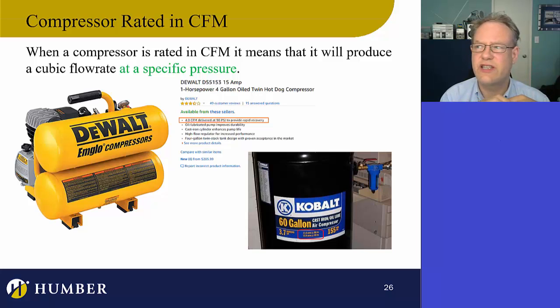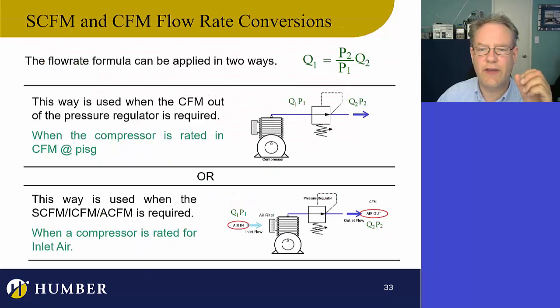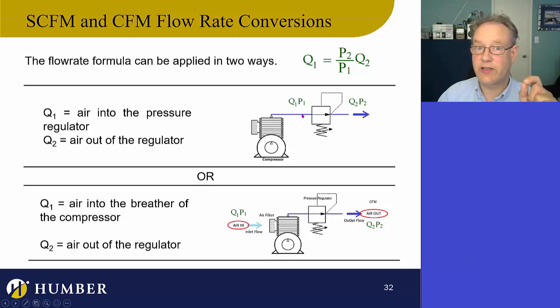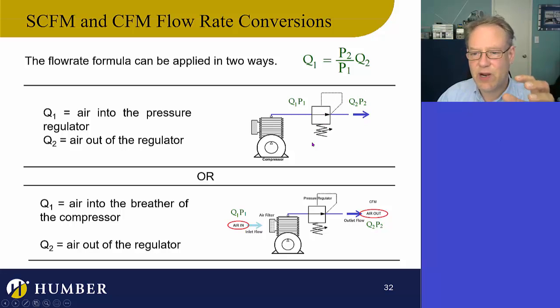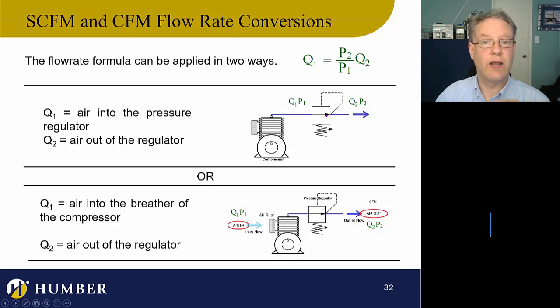When you look at these things, think about what pressure your system uses and how much flow rate you actually need, then do the math. There are two ways: one is a compressor rated for outlet flow, where I can change the pressure regulator. If the manufacturer says at 90 PSI the flow rate will be 4 CFM, but I need it at 70 PSI, I have to calculate if the new flow rate will be sufficient.